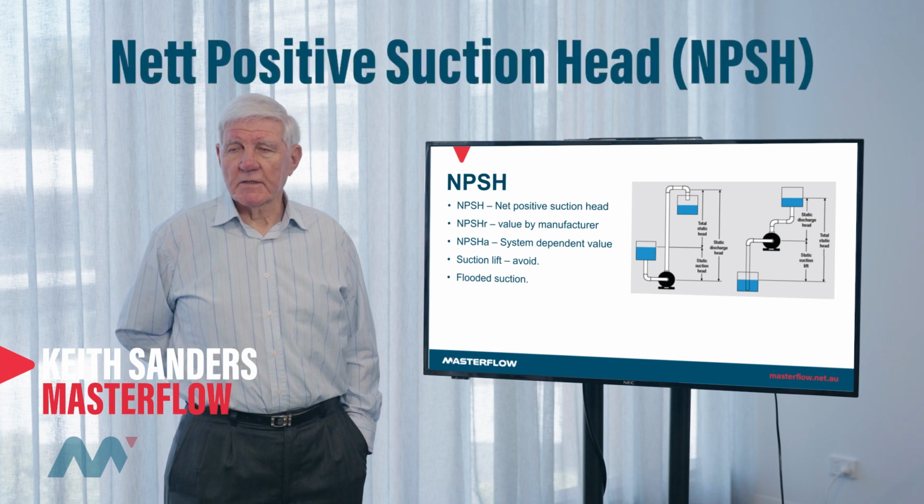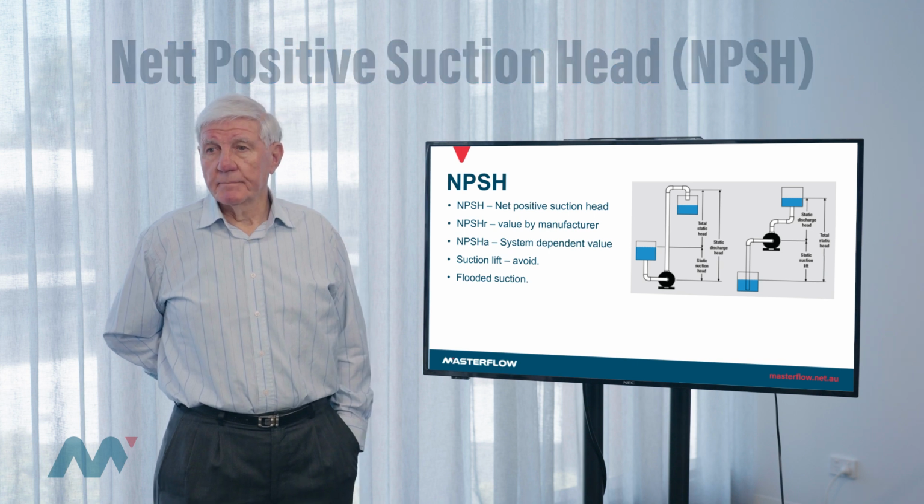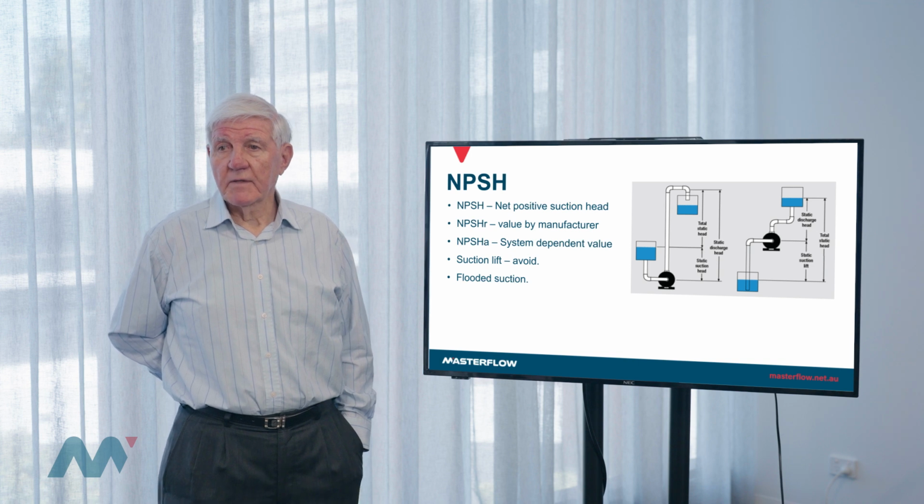It's net positive suction head. In other words, the pressure on the suction eye of the impeller. And that's the lowest pressure in a pumping system, at the actual eye of the impeller. What we've got to do is make sure that that pressure is above the vapor pressure of the liquid at the pumping temperature. Otherwise, we'll get vaporization, which means that the liquid turns from a liquid into a gas. And that's what we call cavitation. So that cavitation process is engendered by the phenomenon NPSH.